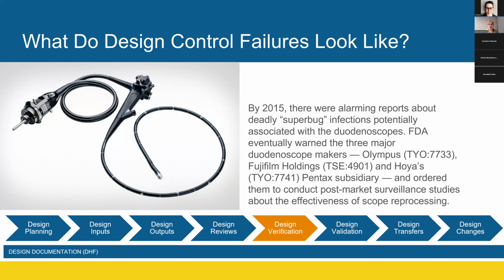An endoscope is a reused device. After it's been used on one patient, it undergoes a whole cleaning and sterilization protocol to make sure it's safe to be used on the next. For devices like this, you actually have to submit your cleaning protocol with your original FDA designation to get the indication of use for reuse. The problem was they did all their cleaning tests on brand new products. Over time, like any device that has some plastic components, some of the plastic started to shrink. You started getting very tiny cracks and crevices in places where material didn't get fully cleaned when using the cleaning protocol developed on a brand new device. Those aged devices were not getting fully clean, and as such, unfortunately, you were getting infection spread.